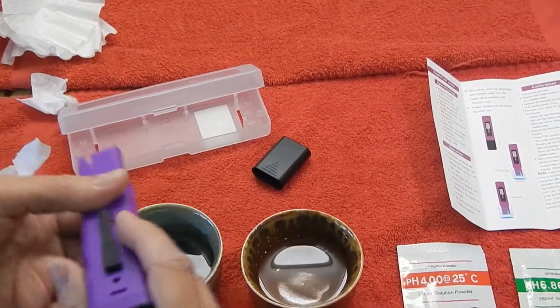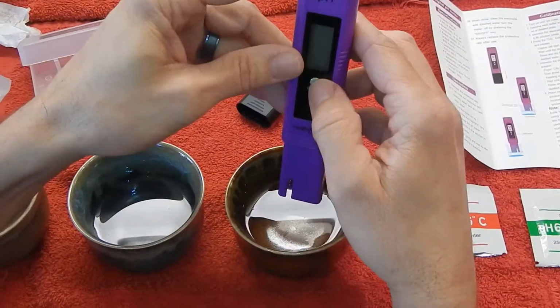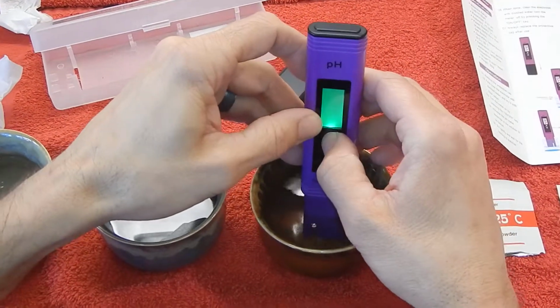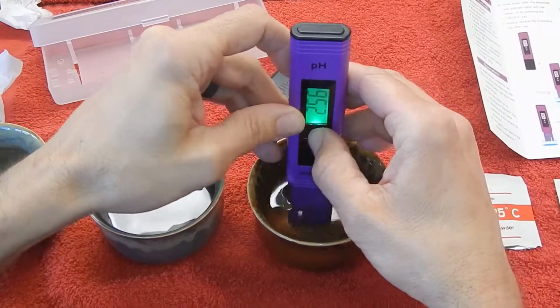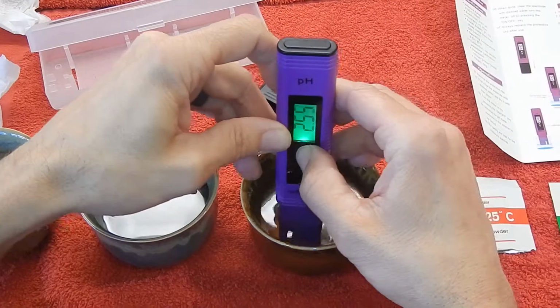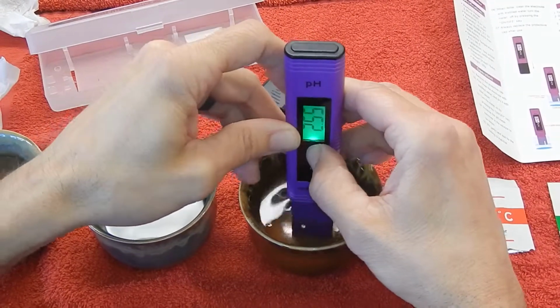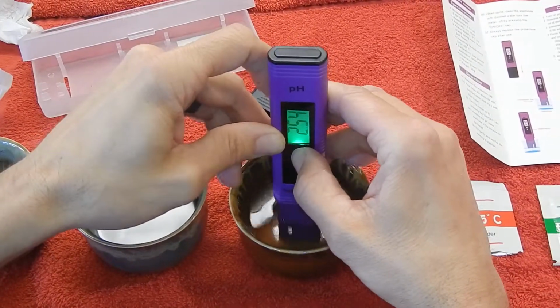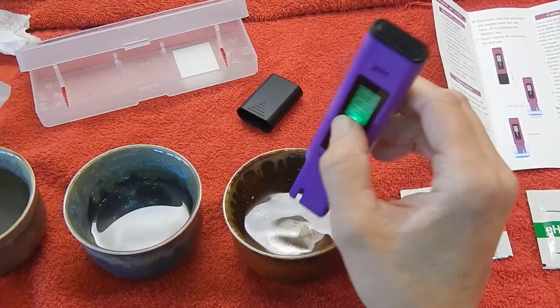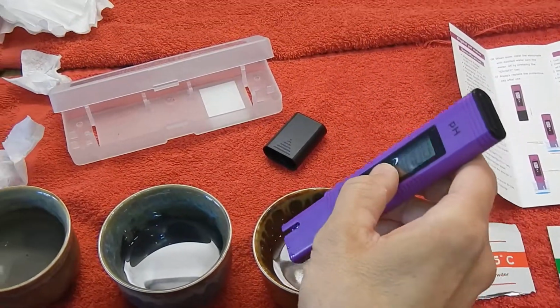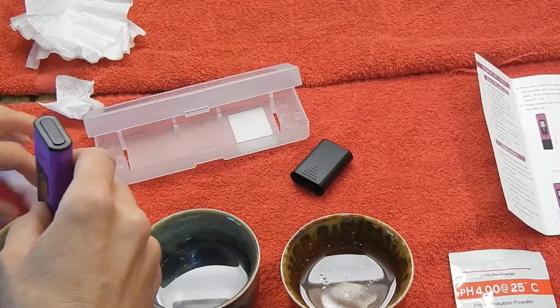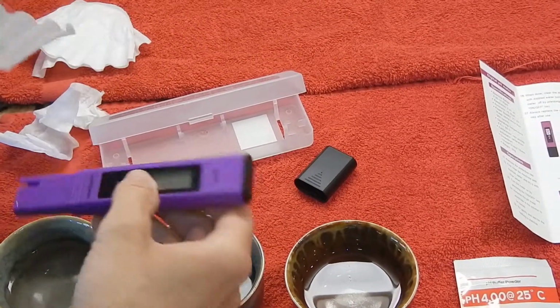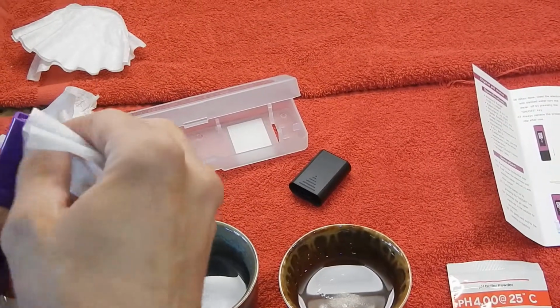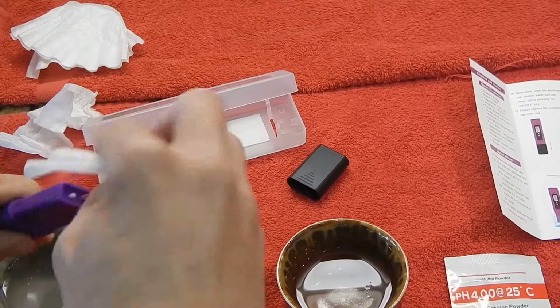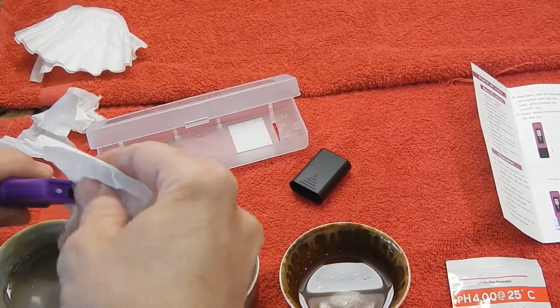So once it's prepared, I'm going to measure the vinegar that we have. So I dip it in the solution, hold the button, and you get a reading of about 2.5. So after I'm done measuring, I again take it, dip it in the distilled water solution to clean it, grab another filter, and blot it dry. And it's ready for my next use.